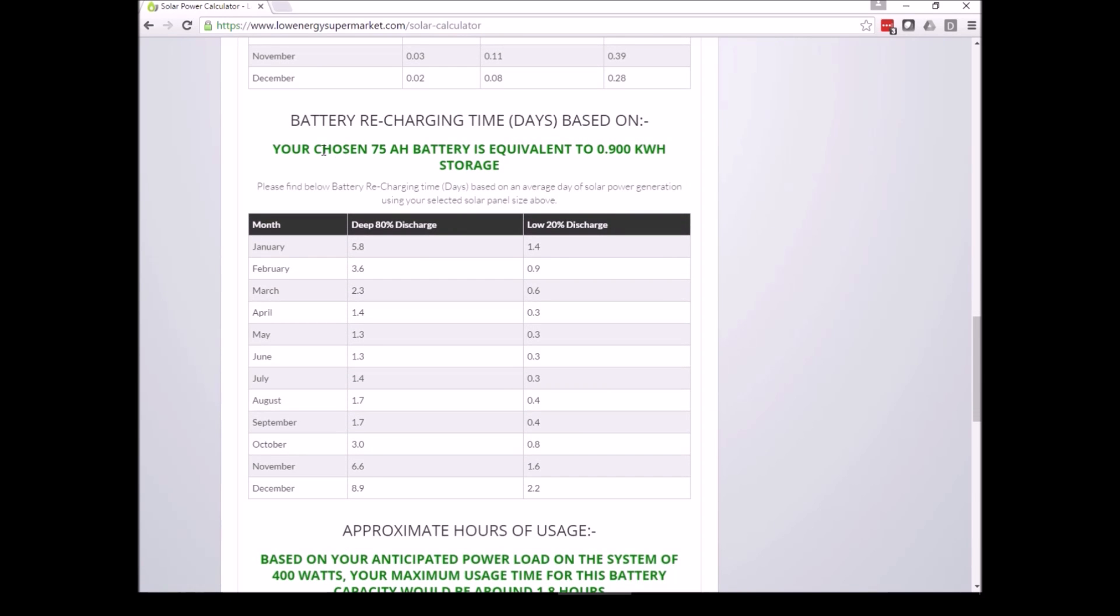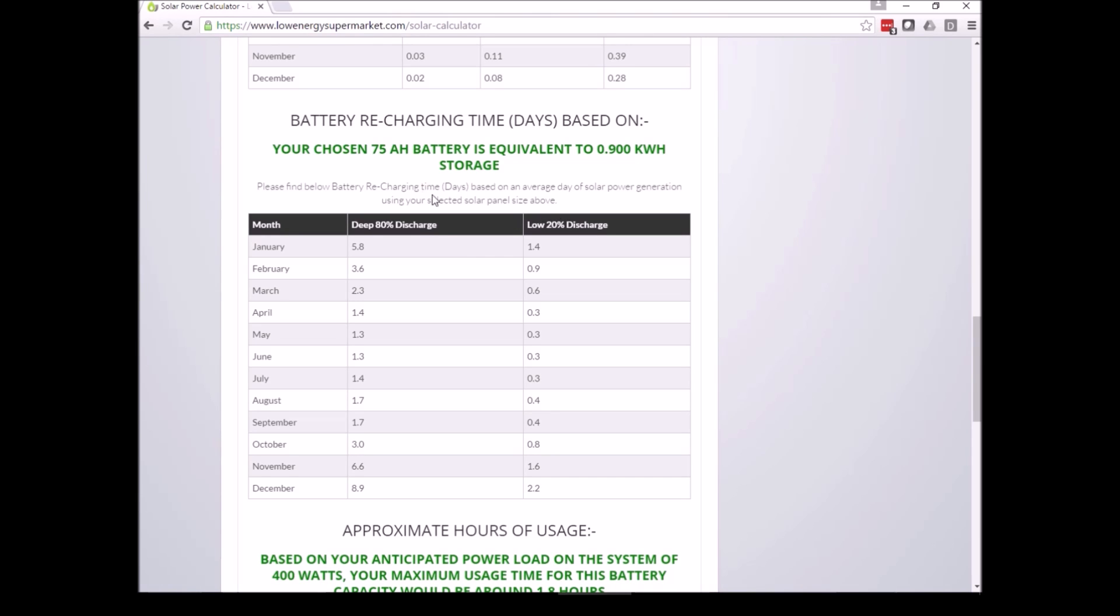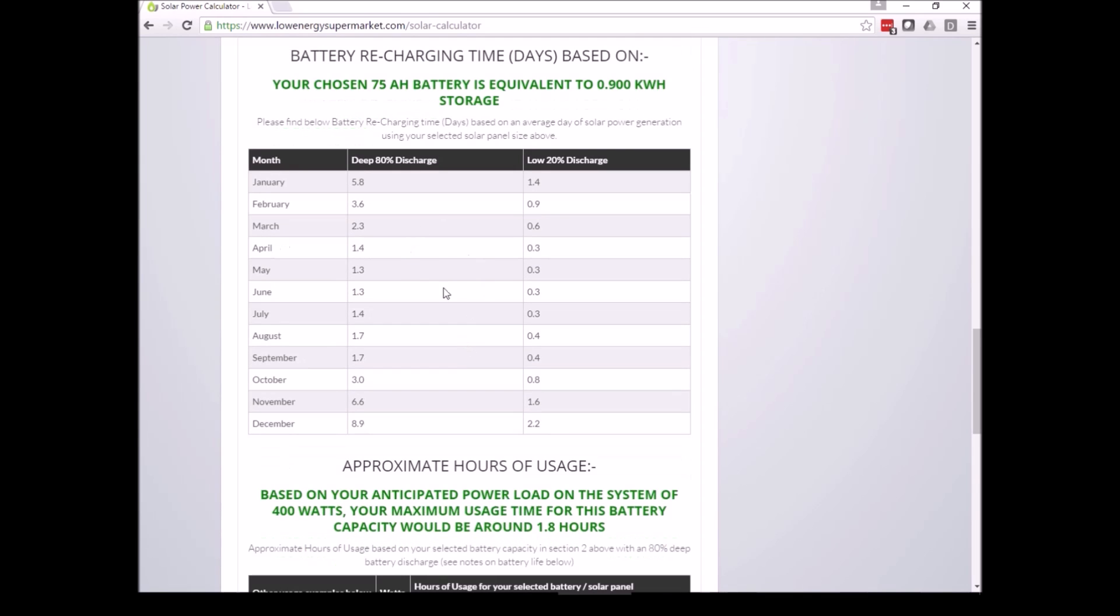The battery recharging time is shown below in the number of days. We've chosen a 75 Ah battery which is equivalent to 0.9 kilowatt hours. At an 80% deep discharge it will take longer to recharge the battery than if you only have a small discharge. A deep discharge could take several days.